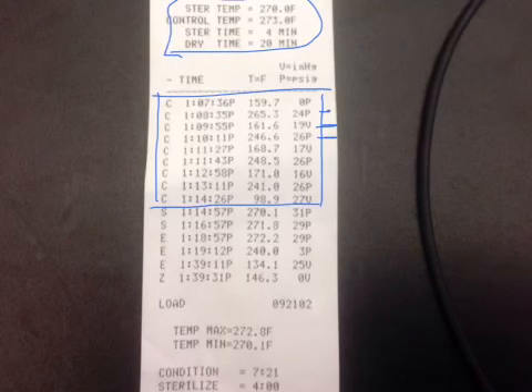Then we shoot a pulse of steam in. It goes up to 246 degrees at 26 psi. And then we pull a vacuum of 17, dropping it back down to 168 degrees. Pulse of steam up to 248 degrees with 26 psi, and then a vacuum, and then a pulse, and a vacuum. So with this particular sterilization prevac, we've got 1, 2, 3, 4 pulses, so that's a 4-pulse prevac cycle.